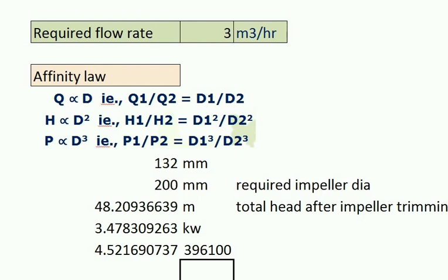Theoretically we get the same, and practically after implementing impeller trimming we also save this much power by the simple trimming of the impeller. It is a very simple process. Our cost will not be more, only the lathe cost and dismantling and assembling. We spent just 4 hours of breakdown, lining up the standby pump, and we get the gain of 3.96 lakhs per annum. It is a big saving.